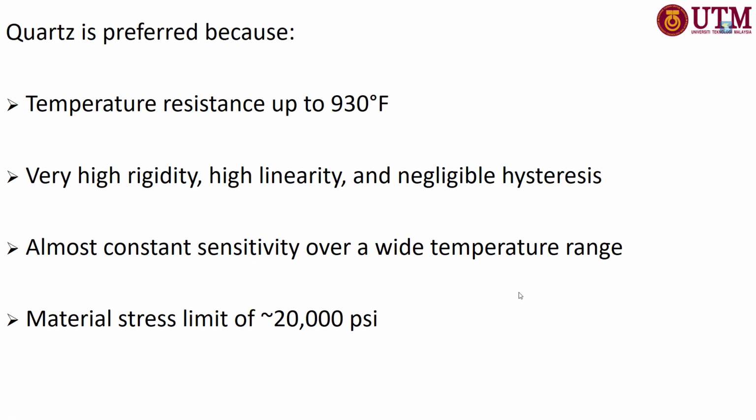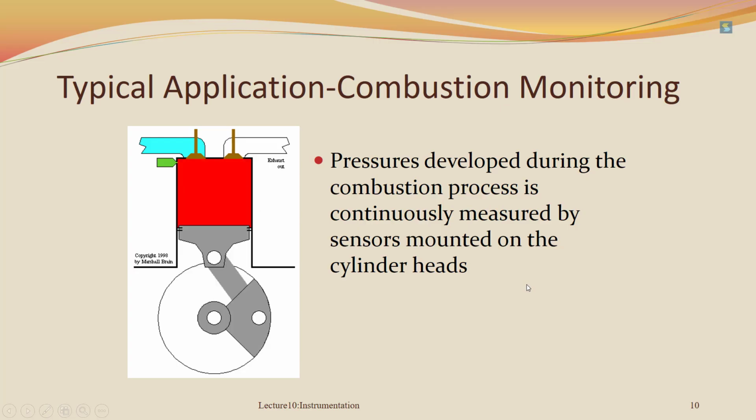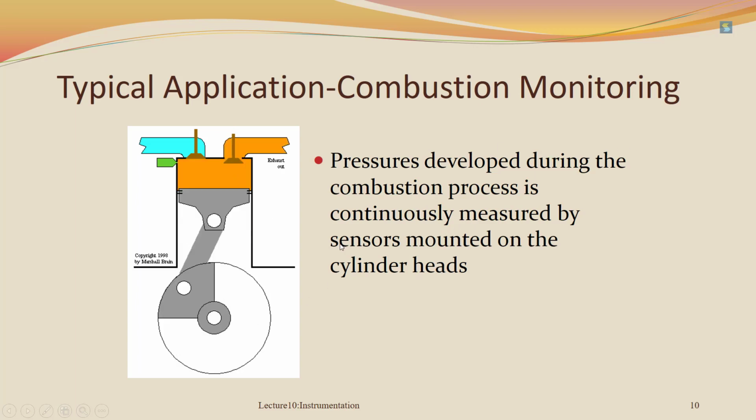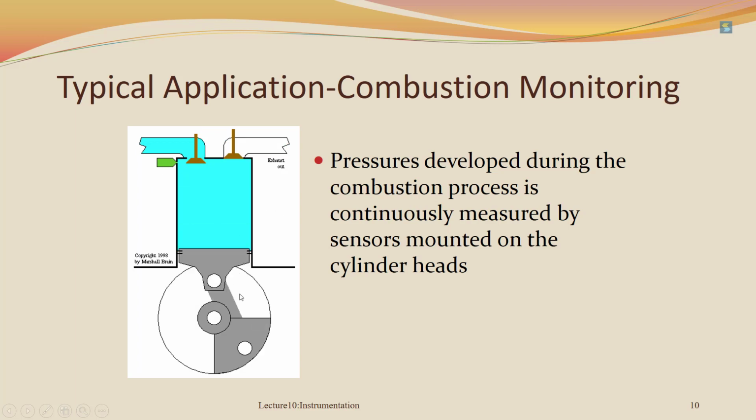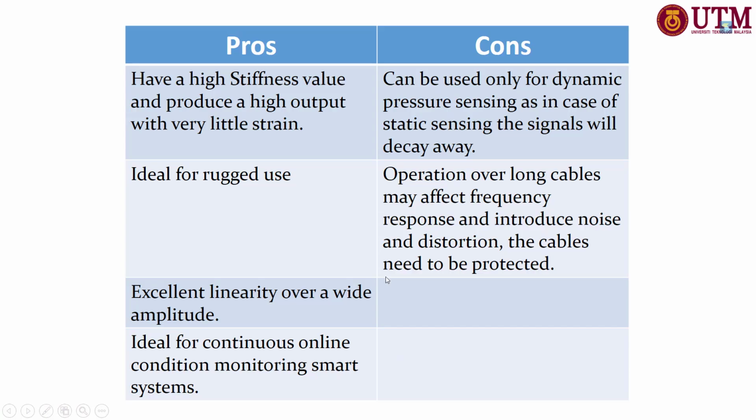For the piezoelectric material, quartz is preferred because of its temperature resistance up to 930 Fahrenheit and so on. And this is a typical application. For example, it has been applied in combustion monitoring, where you can put a piezo there as a pressure sensor, then you can measure how much the pressure of the combustion is. And this is the pros and cons of the piezoelectric transducer.